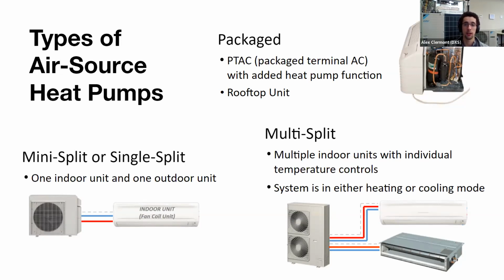Rooftop units can also come as heat pumps. Again, there are some issues with low ambient heating operation with heat pump rooftop units, but they are getting better and they are starting to be more common. If you take an existing mall, for example, with 5 package rooftops serving a specific tenant, if they come to need replacement, you could replace them with electric air source heat pump rooftop units. There are starting to be some good options for those.